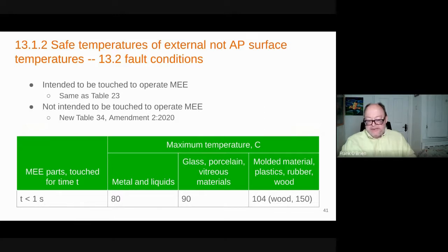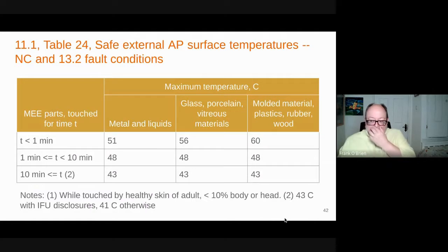But now these are operator surfaces. So if it's an applied part, we wouldn't have this. Applied parts have to meet temperature limits in normal and single fault. So if you think about an ultrasound transducer, if you do a fault where one of those transducers doesn't shut off, it would be a bit warmer. And that's got to stay within the normal limit because it's the applied part. You know, all those transducers multiplex. All right.